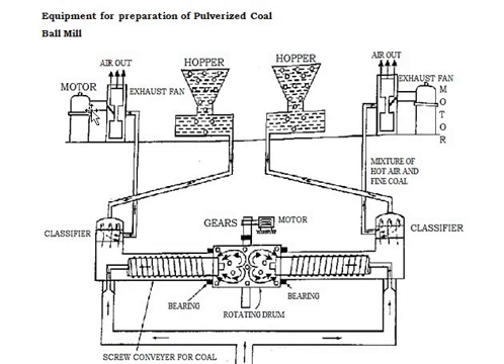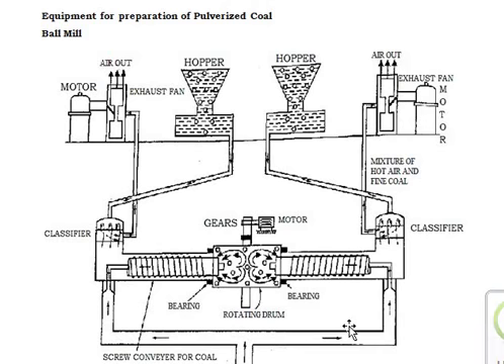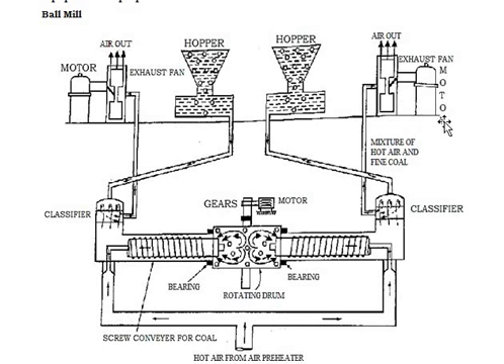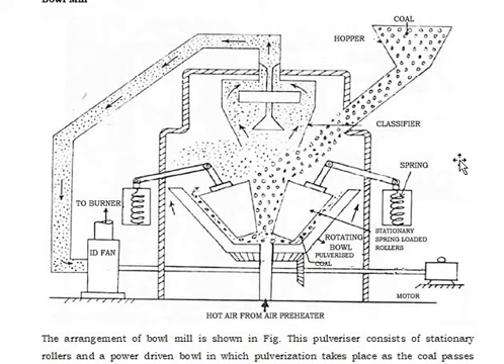Next, the equipment for preparation of pulverized coal: the ball mill. You can see the ball mill here with the motor, two hoppers, a classifier attached to both hoppers, a gear motor, bearings, and a rotating drum. You can also see the screw conveyor through which coal is conveyed with the help of hot air from the air preheater, and an exhaust fan which throws exhaust material outside.